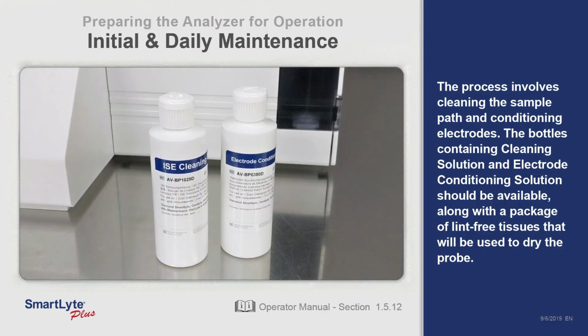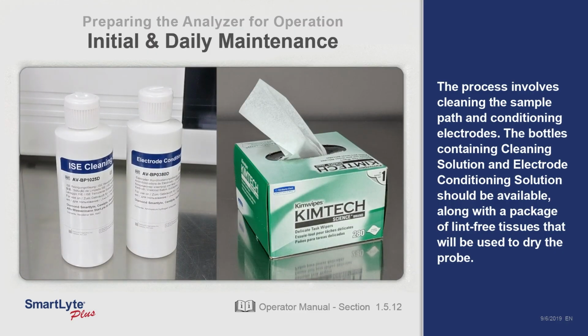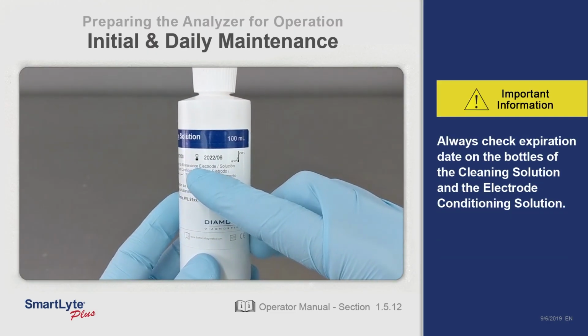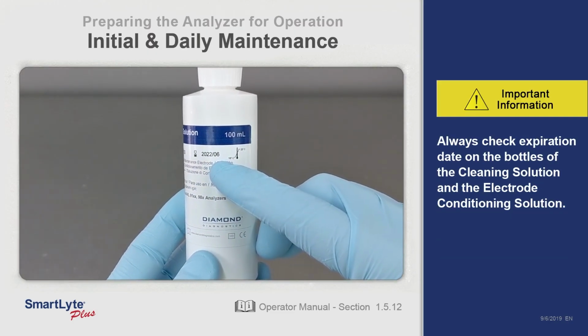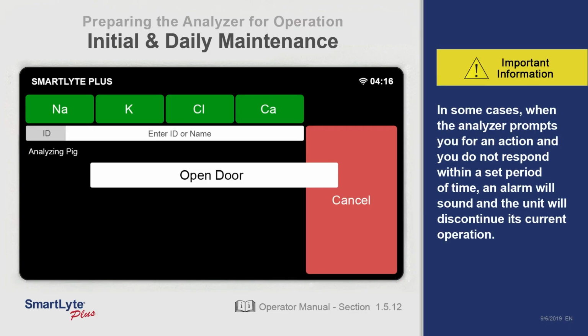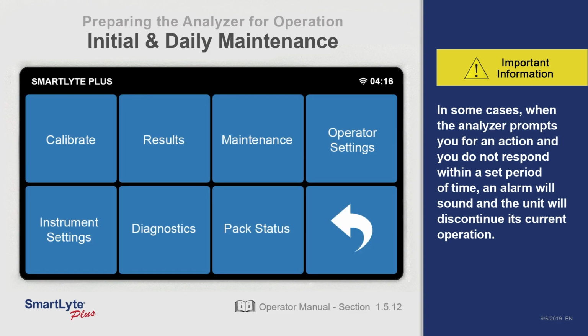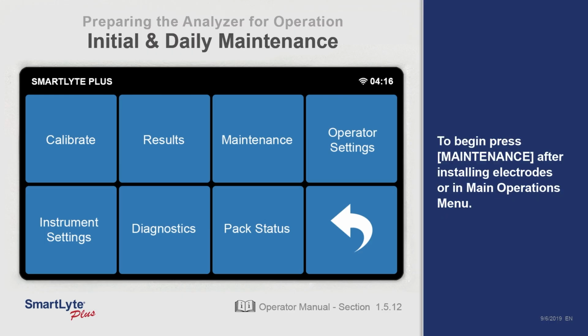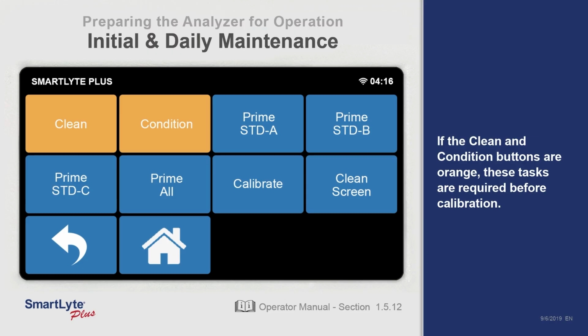The bottles containing cleaning solution and electrode conditioning solution should be available along with a pack of lint-free tissues that will be used to dry the probe. Always check the expiration date on the bottles of the cleaning solution and the electrode conditioning solution. In some cases, when the analyzer prompts you for an action and you do not respond within a set period of time, an alarm will sound and the unit will discontinue its current operation. To begin, press Maintenance after installing electrodes or in the main operations menu. If the Clean and Condition buttons are orange, these tasks are required before calibration.